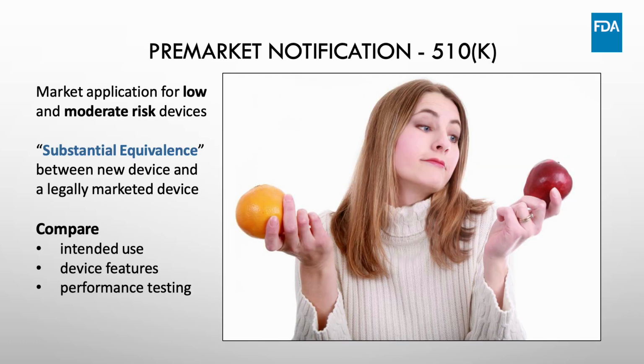Next, we'll highlight the pre-market notification, commonly known as 510(k). The 510(k) is the most prolific pre-market submission type, with several thousand 510(k)s submitted to FDA each year. This is a marketing application mostly for low and moderate risk devices. These are the ones that are class 1 or 2 typically.